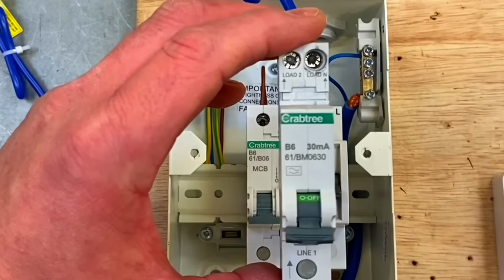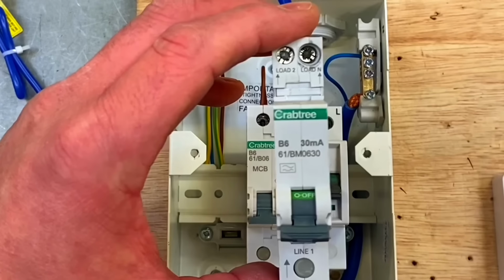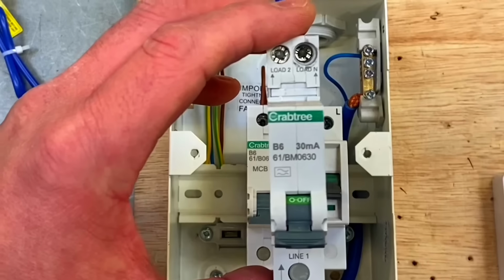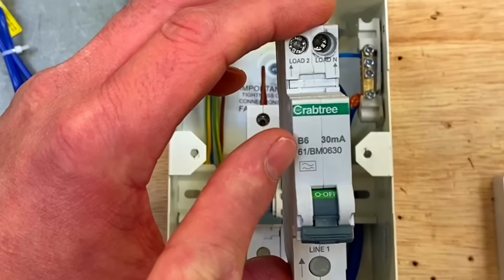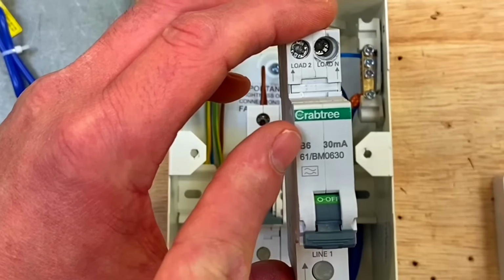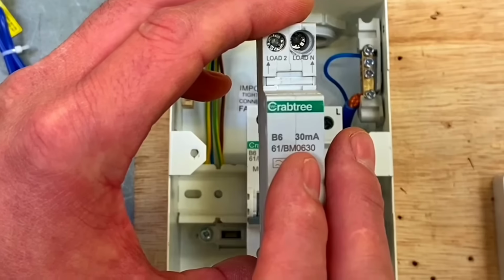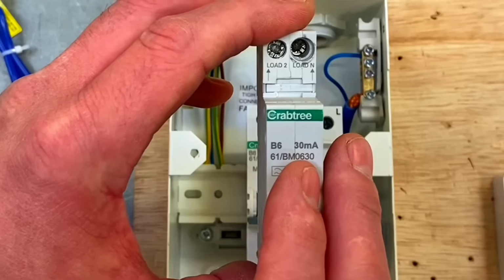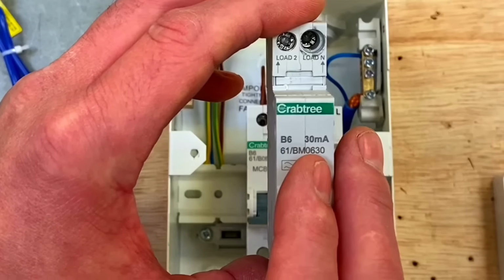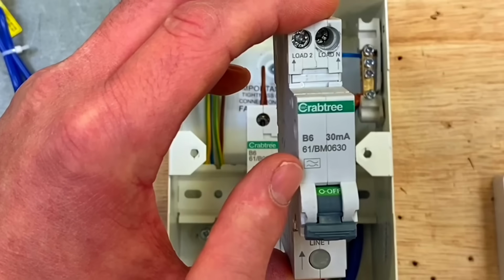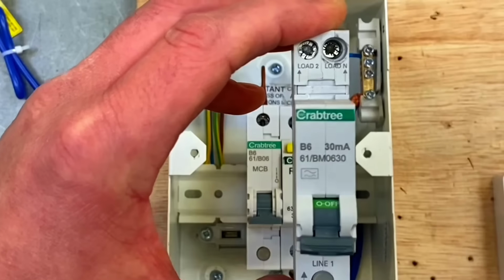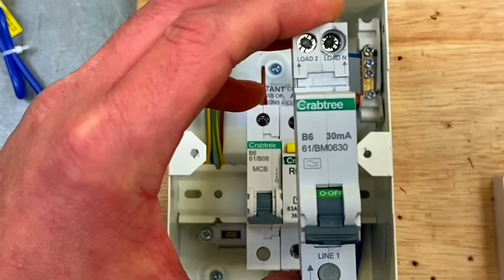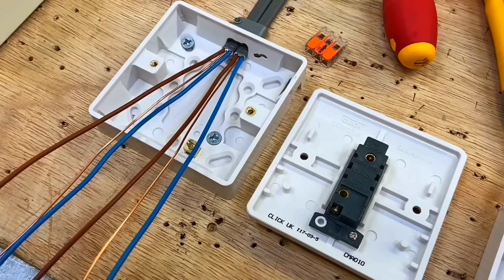So we've got both the overcurrent protection device of a circuit breaker and the additional protection offered by an RCD in one unit. Again, B6, type B, 6 amps, rated at 30 milliamps. So again, for additional protection, rated at 30 milliamps or less. And this time we do like this one because this is an A-type device, and we're looking to move towards more A-type devices, something we've talked about a lot in the classroom. So we're at the switch now.